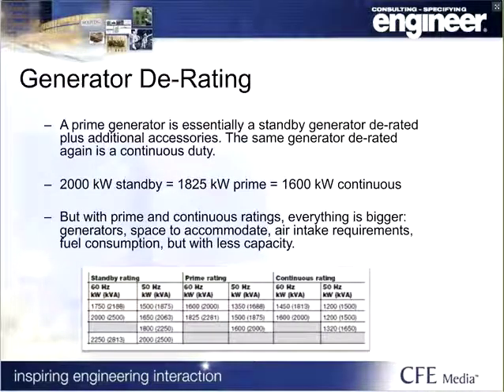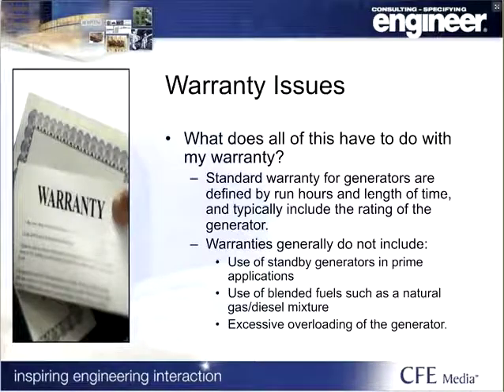This is kind of what happens. We're looking at a generator cut sheet. It's the same generator, the same build, but a 2000 kW standby generator is actually rated 1825 prime, which is actually also 1600 kW continuous. So as I extend the full load runtime, I cut my capacity of the generator. So, what does this have to do with your warranty? You have specific language written into your warranty for peak load and a certain amount of time. So if you're planning on running it at that rate, then you need to make sure you plan for that. And it certainly does take size.